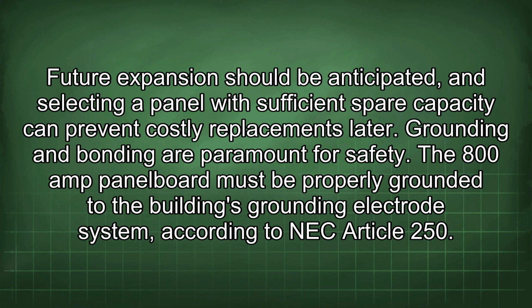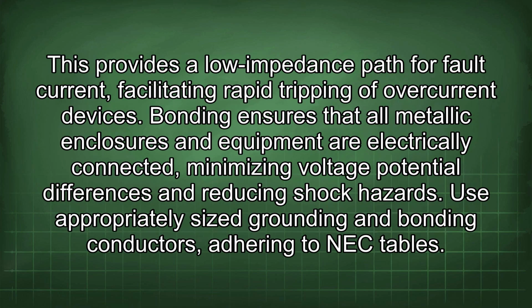Grounding and bonding are paramount for safety. The 800 amp panel board must be properly grounded to the building's grounding electrode system according to NEC Article 250. This provides a low impedance path for fault current, facilitating rapid tripping of overcurrent devices. Bonding ensures that all metallic enclosures and equipment are electrically connected, minimizing voltage potential differences and reducing shock hazards. Use appropriately sized grounding and bonding conductors, adhering to NEC tables.